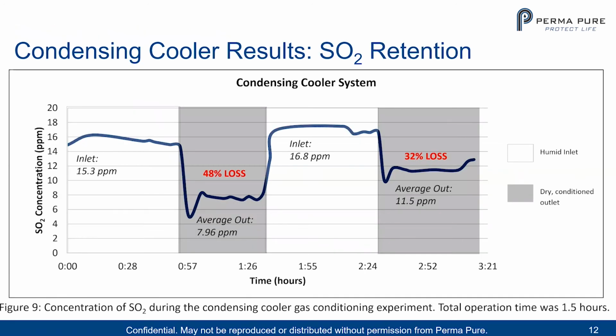Now let's look at the results of the condensing cooler system. This is our A-B results. You could see the basic SO2 concentration that was generated by the humidified calibration gas was roughly 15.3 parts per million. When we turn on the cooler, our average out was 7.9 parts per million for a 48% loss. When we turned off the cooler, we went up to 16.8 parts per million. We turned on the cooler again. We got to 32% loss, roughly 11.5 parts per million. Okay, so that's the difference between your inlet and your outlet of the cooler.